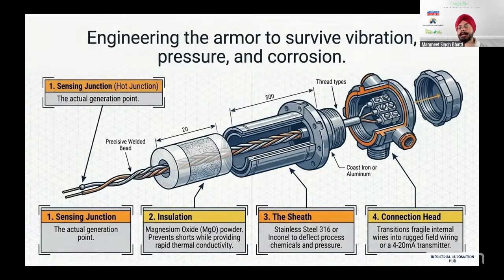So we have seen the metal is very simple metal. That is the way it is going to work. But that metal needs to be protected, because when the sensor is installed into the field, there is too much heat coming out, there is too much pressure, there is too much vibration coming on it. So we need to protect that sensor. If you see the complete breakdown of this entire thing, number 1 is called the hot junction. This is the point where the actual generation of your voltage will start when the temperature goes up.